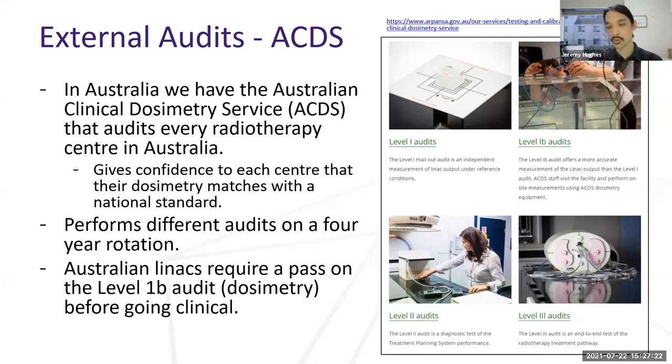And level two audits are basically a more complex machinery and more complex treatments. And level three is you're doing lots of different patient-like treatments just to verify that your delivery is what you've planned.